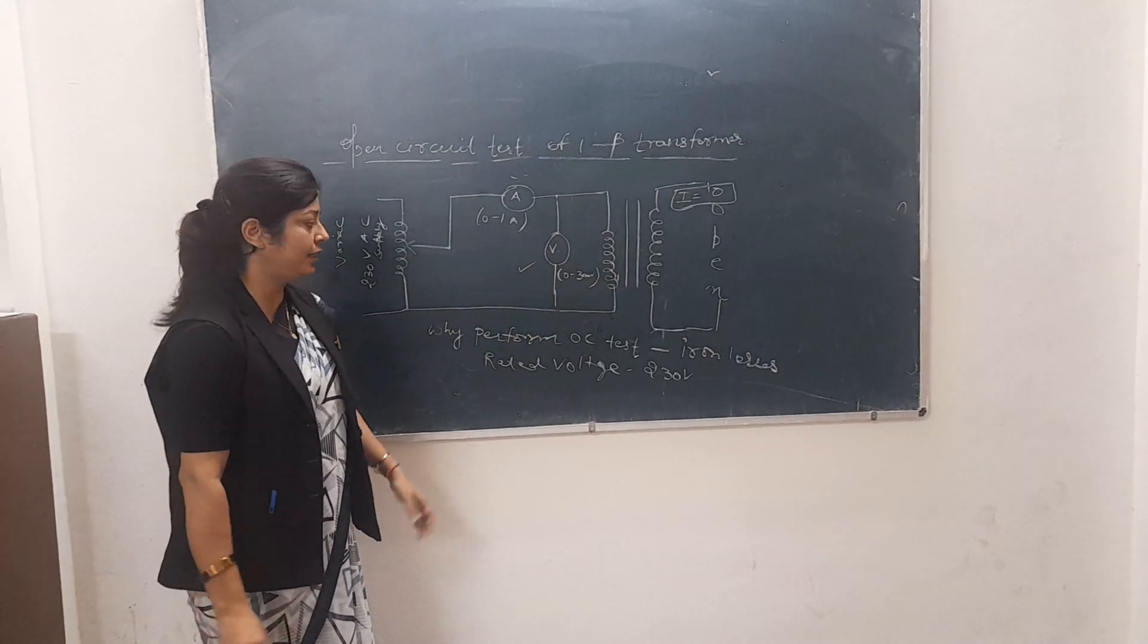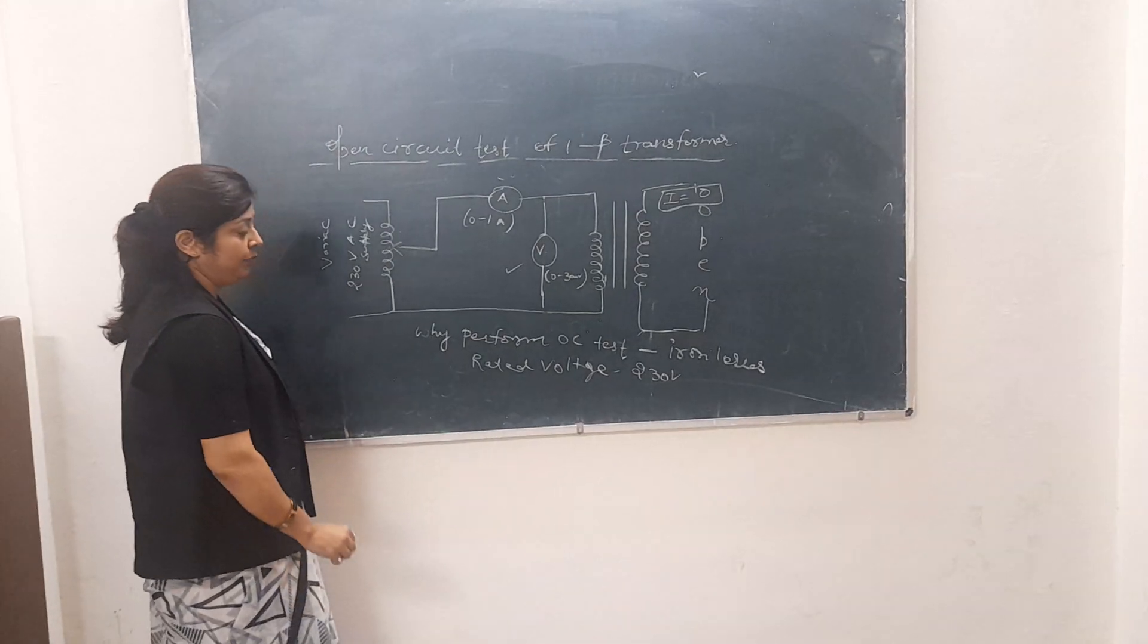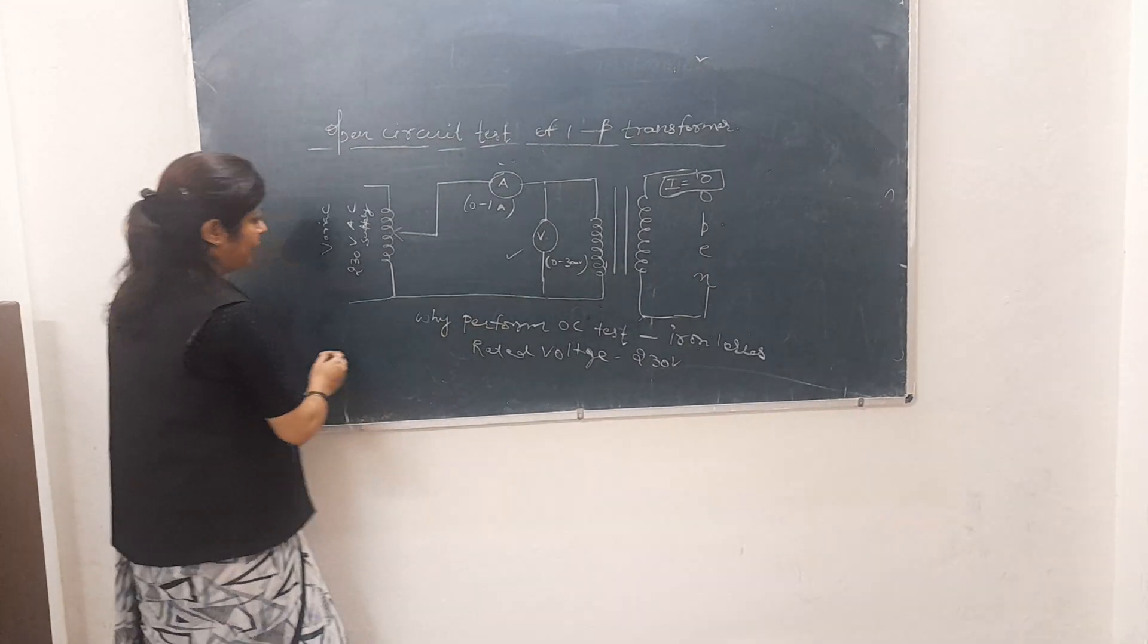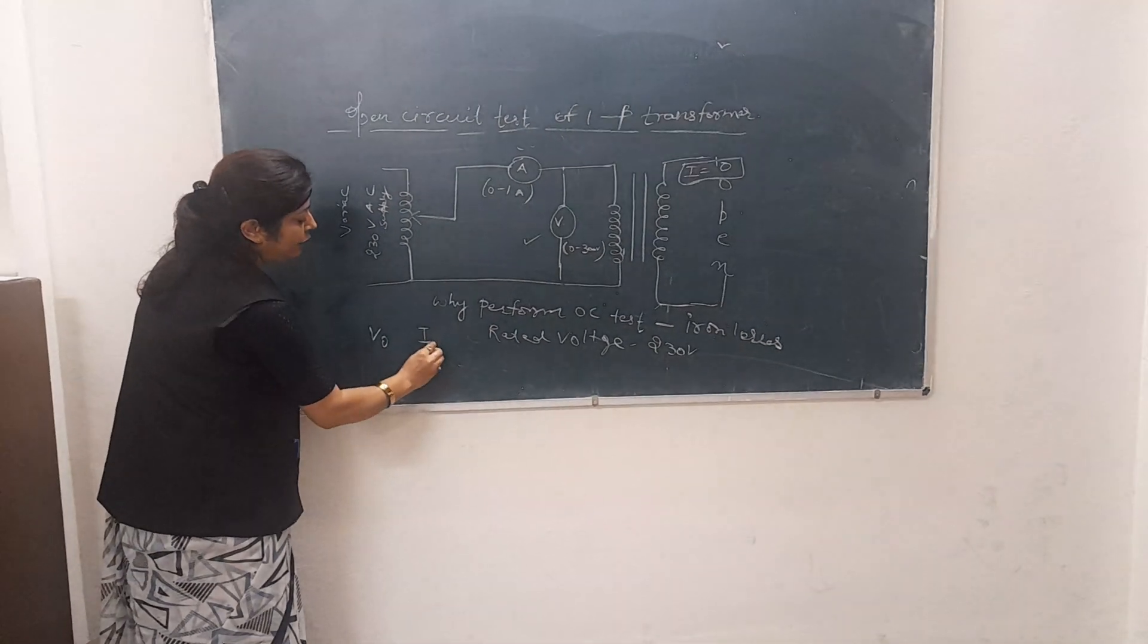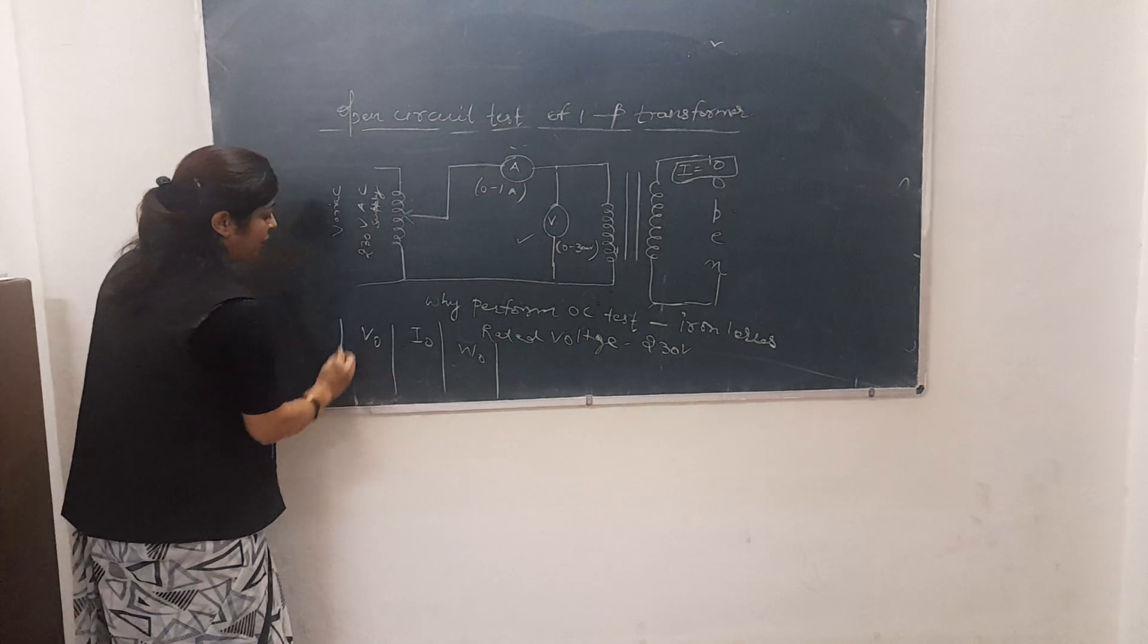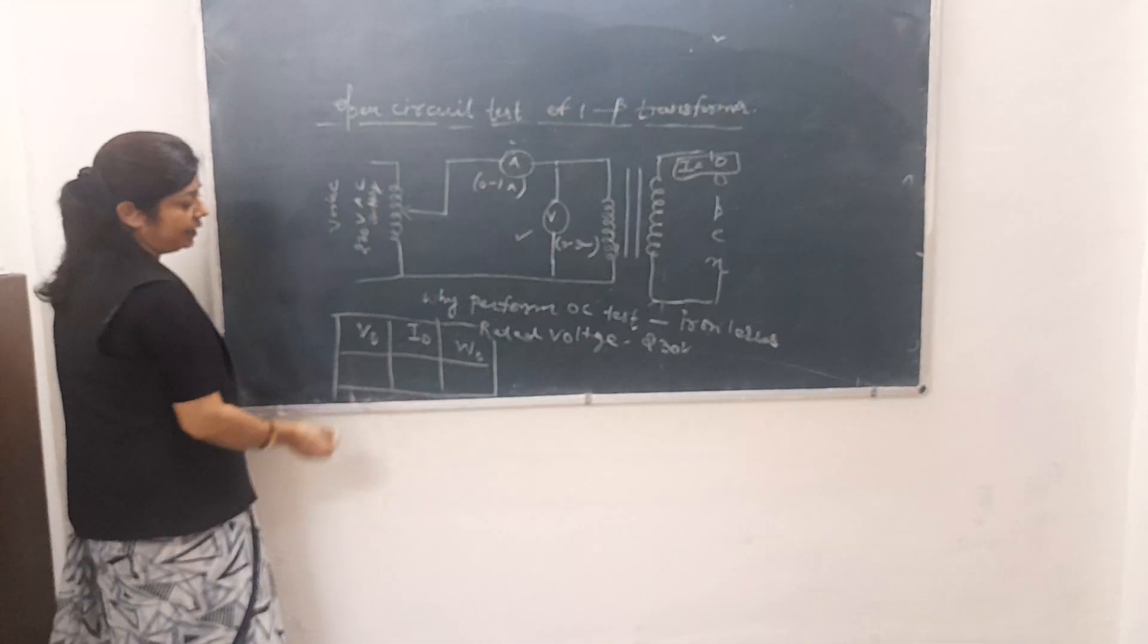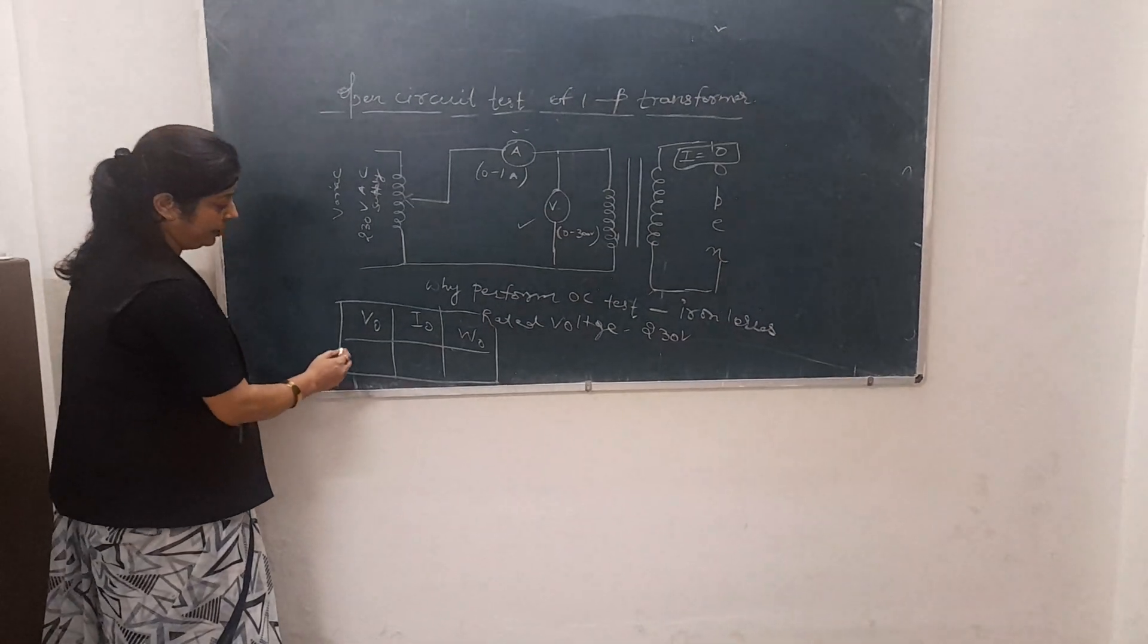You will see how many iron losses there are. We are using rated voltage. The parameters are called V0, I0, and W0, where V0 is the voltage of open circuit, I0 is the current, and W0 is the iron losses. V0 is already fixed at 230V.